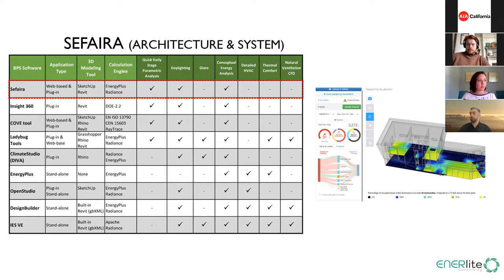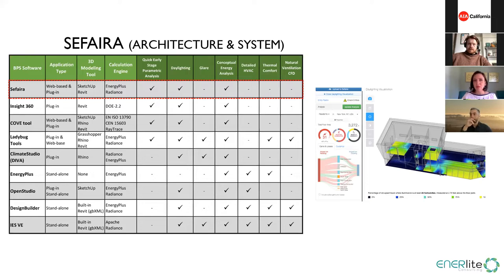Sefaira is a web-based and plugin application for SketchUp and Revit — it works better with SketchUp, for which it was originally designed. It uses Energy Plus as the engine for energy modeling and Radiance for daylighting. It is good for quick early-stage or parametric analysis to see the impact of window-to-wall ratio, R-values, and orientation on building energy consumption. It is good for daylighting and provides some conceptual energy analysis. It does not support detailed HVAC, thermal comfort, or CFD.